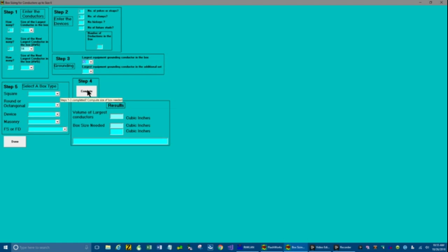Go to step 4. Click the compute button. And it's calculated. The volume of the largest conductors is 4.5 cubic inches. The box size needed is 17 cubic inches. So let's see what kinds of boxes we could use.